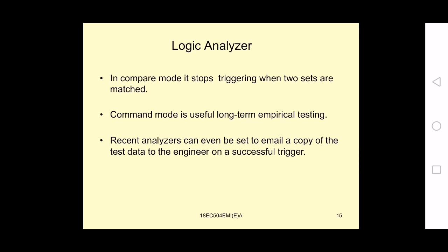Compare mode is useful in long-term empirical testing. Nowadays, recent analyzers can even be set to email a copy of the test data to the engineer on a successful trigger.